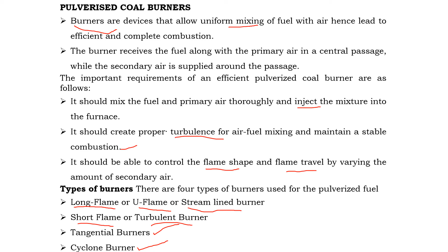The arrangement of the long flame U-shaped burner is schematically shown in this sketch. The burner is placed such that it produces a long U-shaped flame. You can see from the sketch, this is the U-shaped flame. The burner injects a mixture of primary air and fuel vertically downward in a thin stream, practically with no turbulence, and produces a long flame. Secondary hot air is supplied at right angles to the flame, which provides necessary turbulence and mixing for proper and rapid combustion. A tertiary air is also supplied around the burner for better mixing of fuel with air.